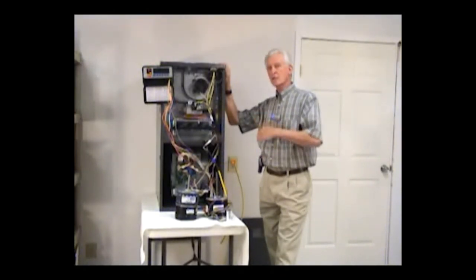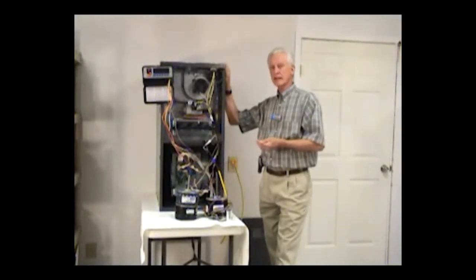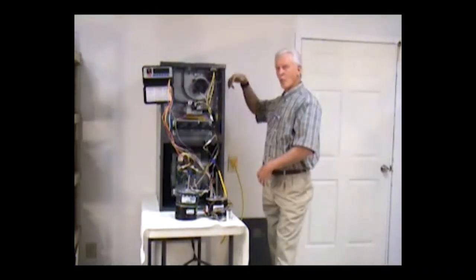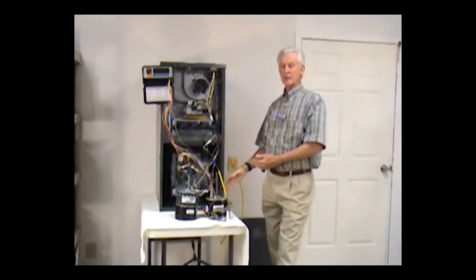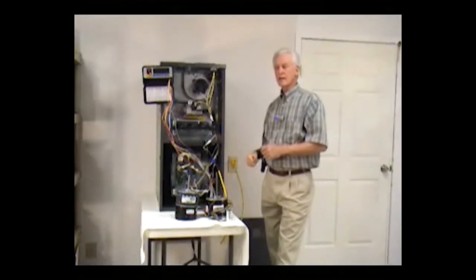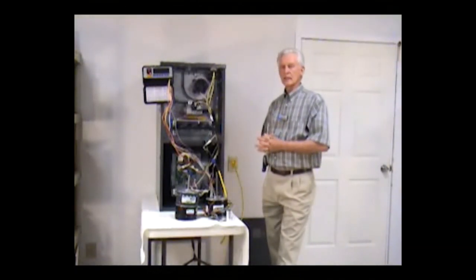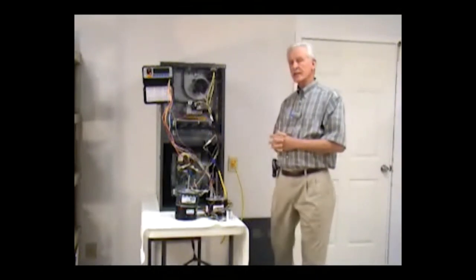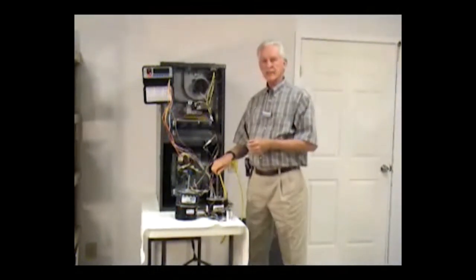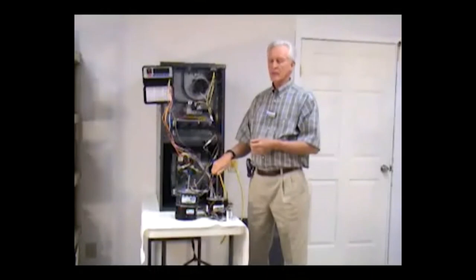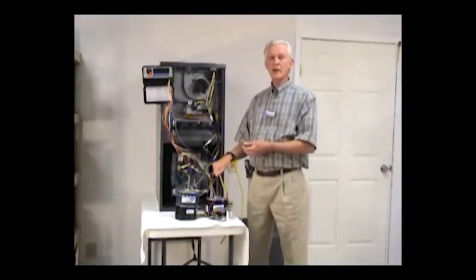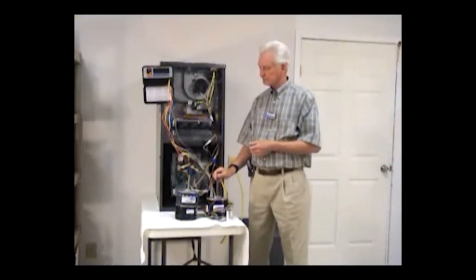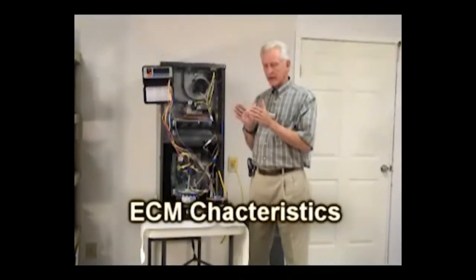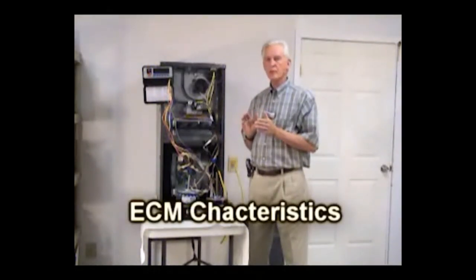So it's kind of backwards of what we are normally thinking as a technician in the field, that the more ductwork, and if we have filtering systems and we have return air, that actually is increasing the load. The amperage draw does drop slightly at that particular point when we go above 0.5, and then when we go below 0.5, now we are able to move more air with this motor because it does not have near the resistance to it, so the amperage draw goes up slightly on it. It gives us a very, very small range for us to operate in.